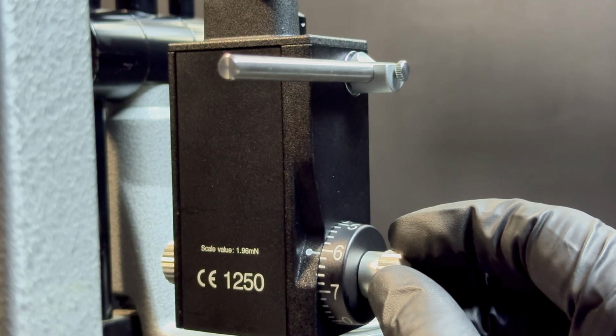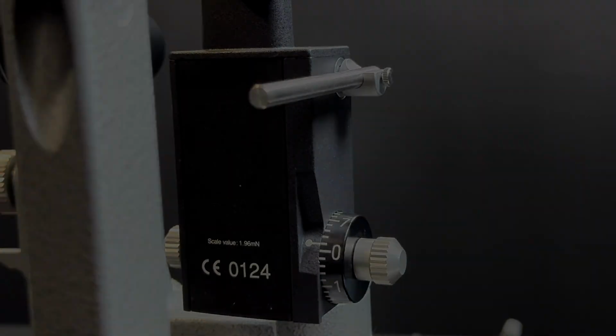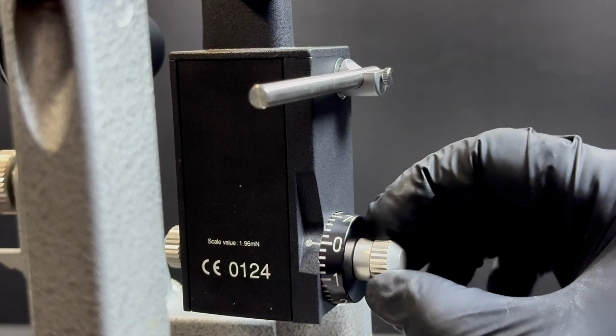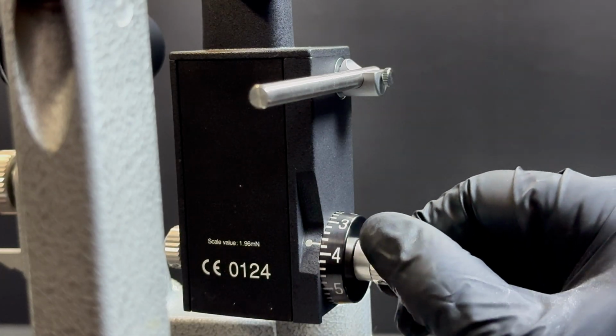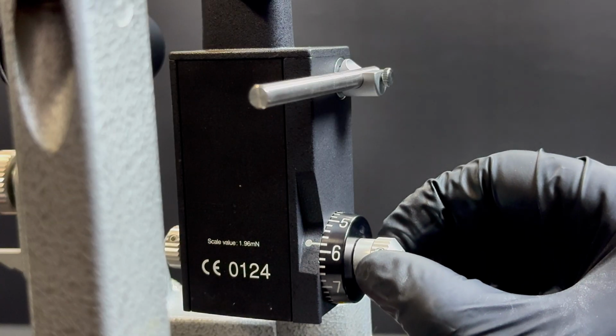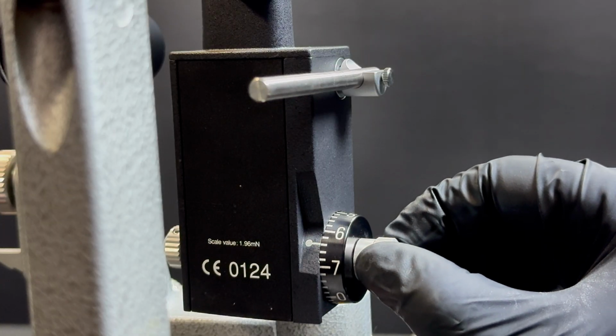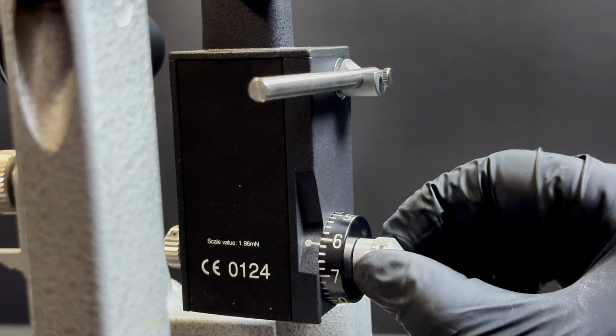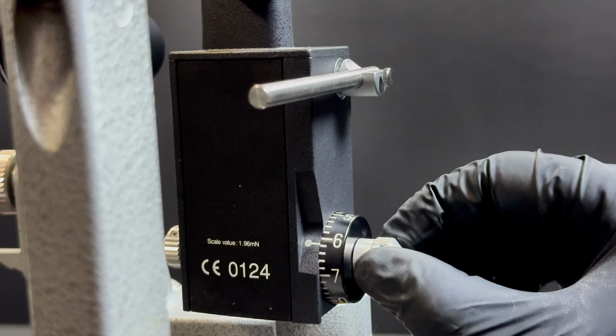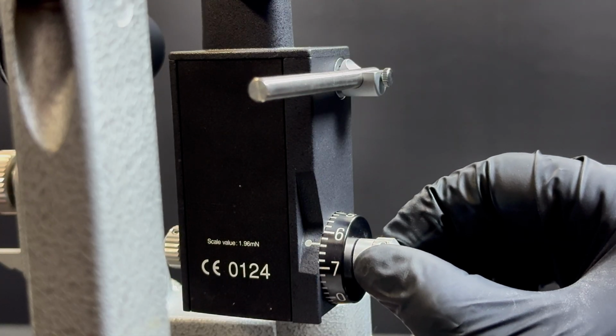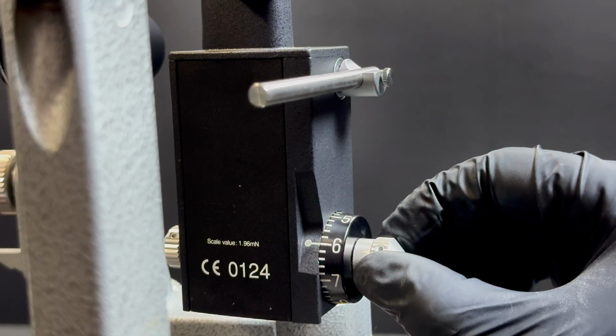If the feeler arm moves far past the 6 mark or drops before reaching it, the tonometer is out of calibration. Here is an example of a tonometer that is out of calibration with a late drop. When checking the 6th setting, the test bar does not move until well after passing 6 and returns to neutral while still beyond the 6 mark. Because the test bar drops late, this tonometer is out of calibration and requires service.